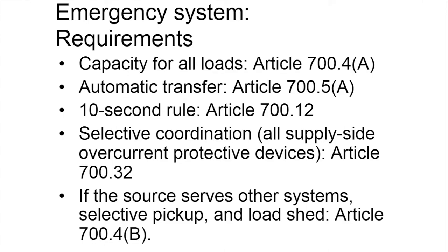Proponents of this requirement argue, from a philosophical standpoint, that selective coordination is necessary to maintain safety, and opponents of the requirement claim that there's no record of anyone ever being injured by a failure of coordination, and that a super commitment to selectivity will drive all of the design decisions about the system to the exclusion of other important factors. The requirement for selectivity first appeared in the 2005 edition, and since then it's led to a lot of lively discussion. The requirements got amped up in the definition of selective coordination in Article 100 in the 2014 NEC, and they now say that full selective coordination is required at all times and for all currents for all the devices upstream in the system. Later, we'll see how this requirement gets modified for healthcare systems.